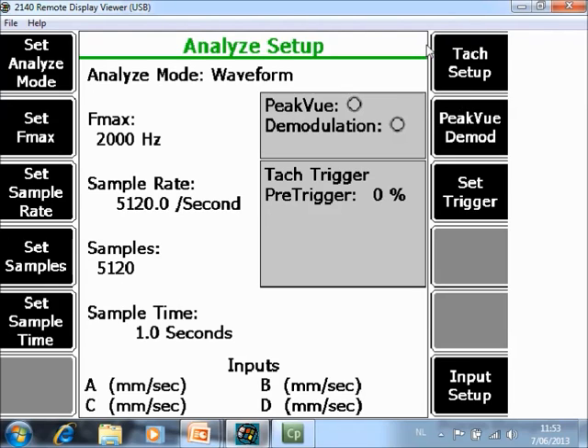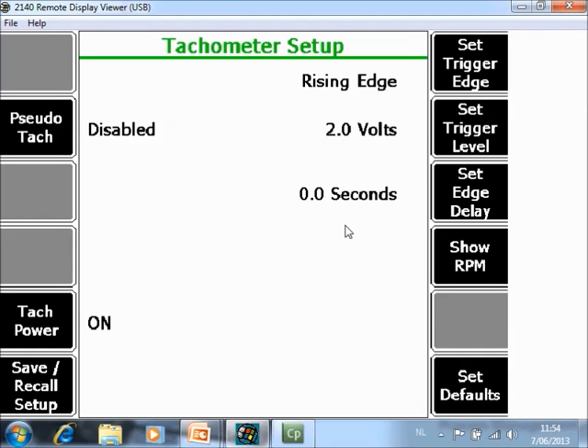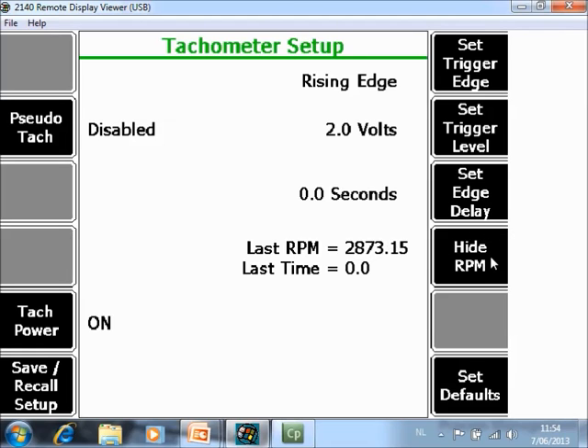In Tach Setup, if you have a tach installed and you configure it here properly, also speed information will be measured and stored. So F7 Tach Setup. In this example I am using a traditional photo tach so the power is ON and a positive pulse of 2V will be considered as a trigger level. To make sure that the tach is working, you can check it immediately by F10 Show RPM. As you see, the speed is coming in correctly so the tach is working.